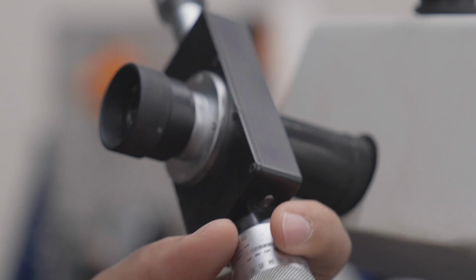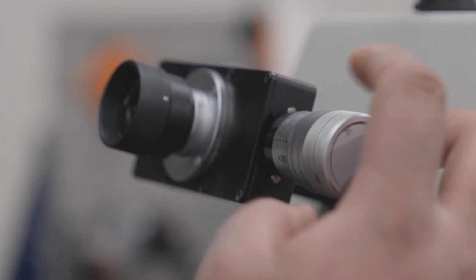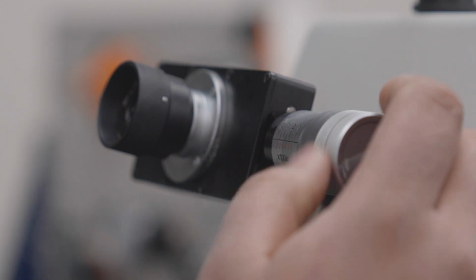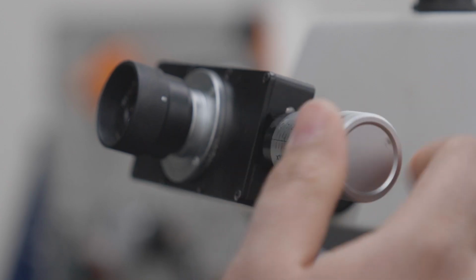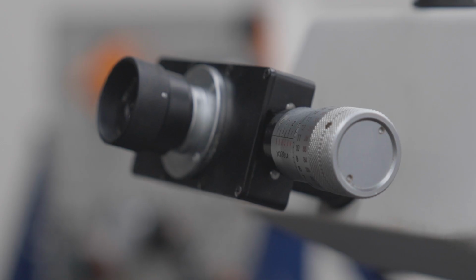So again, you can rotate the visor if you need to align with your indent, and you can move the 2 lines that you see inside the visor. At least one of the lines aligns with one side of the indent, and then the other side needs to be aligned by moving this knob. This will move the one line. When that line is aligned, you are going to read the data of your dial right here.